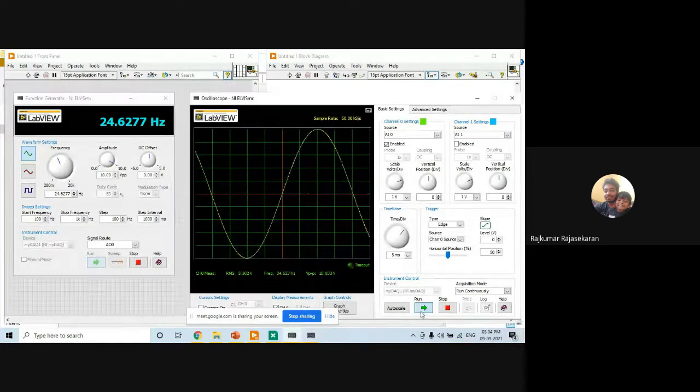Okay, I didn't run it. Sorry. Yeah, if you compare it with immediate, immediate keeps on moving. There is no synchronization. But if you see edge, it's always going to start from this location because you've given the level as 0. You're saying channel source, from this source, this much distance should be there. Something like that.